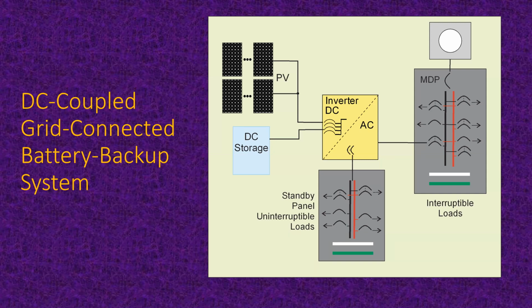And you don't want more than 150% of that rated output power of the DC storage. That's all the PV you want. Otherwise, you're going to be wasting your PV, partly because the connection to the utility won't let it all go through. So, if you don't use it all on your standby loads, then it gets wasted. At least some of it will. So you've got to be careful on your design to get it right and not have too small a storage or too big of a PV to go along with this particular inverter and these particular standby loads, okay?